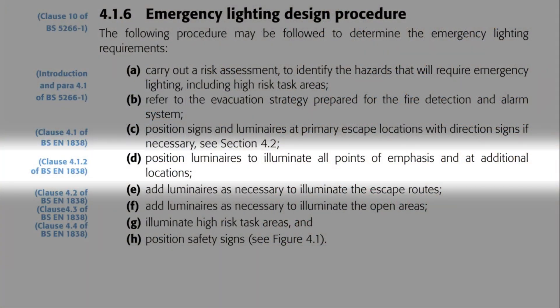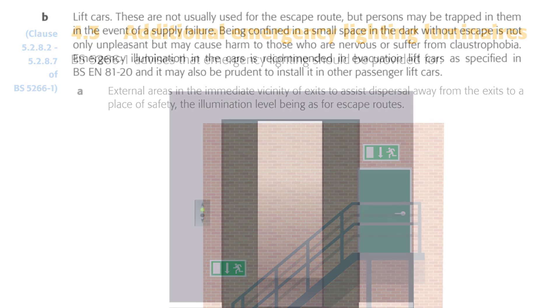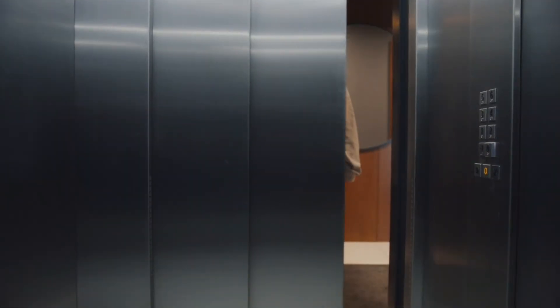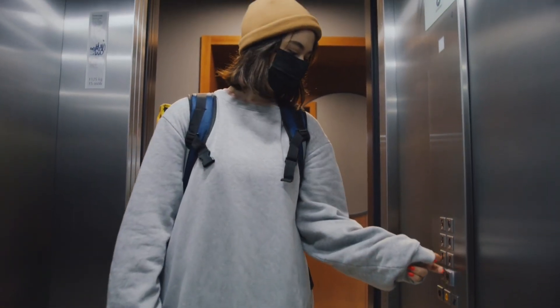Indent D also mentions additional locations covered in their own subheading in the guide. The first re-emphasizes emergency lighting outside emergency exits with sufficient lighting to get people to safety, noting that the illumination level should be the same as escape routes. Lifts also require emergency lighting — even though they're not generally used in emergencies, people may be trapped in them if the power fails and emergency lighting will help them stay calm.